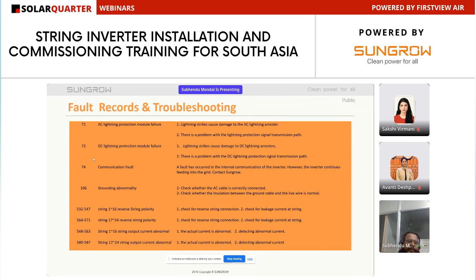Before doing any troubleshooting activity, you have to ensure that the inverter is in off condition. By the mobile app, we have to send the shutdown command to the inverter, then the inverter switch should be off. Then only can we turn the AC side off, and then we can do any troubleshooting activity. We can check any activity with proper PPE. All troubleshooting activity should be done using proper PPE and proper tools.